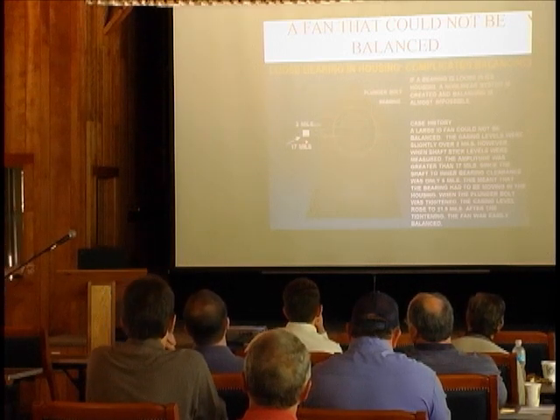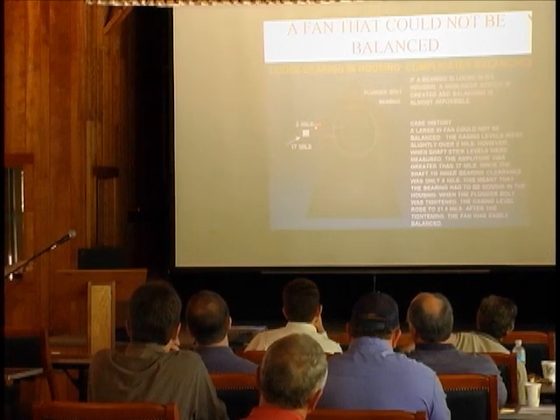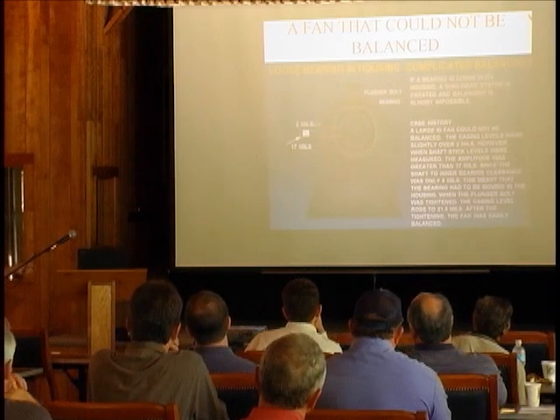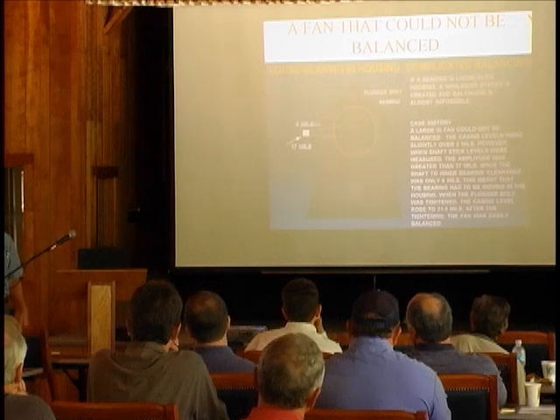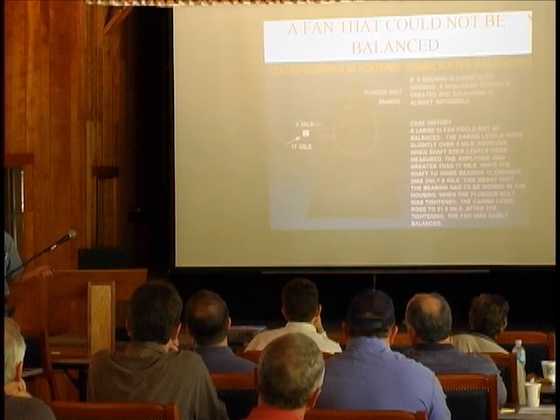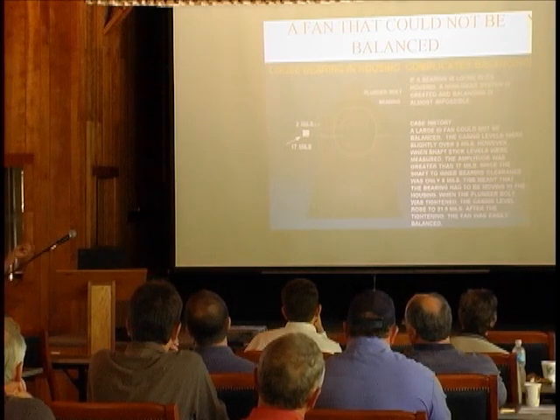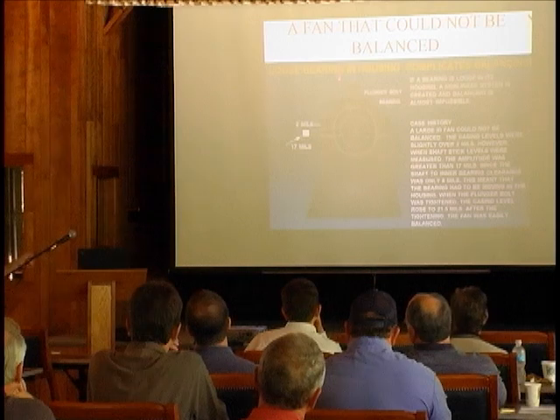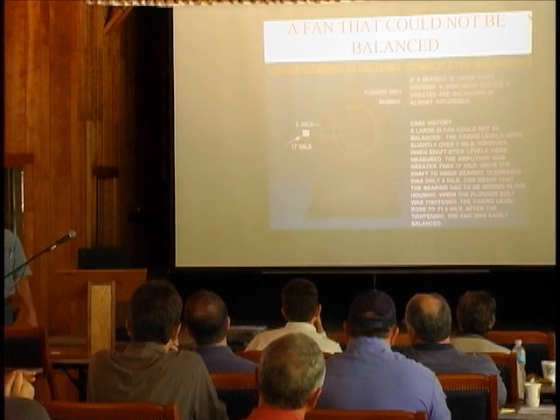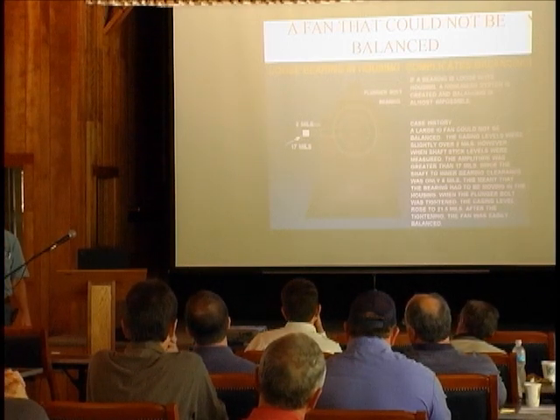So anyway, there was 2 mils on the casing, but when I took the shaft measurement, there's 17 mils. Well, there's only 8 thousandths bearing clearance. Well, that don't add up. That dog won't hunt at all. How are you getting that when you only got 8 thousandths bearing clearance? There's only one way, and that's if the bearing's loose in the housing. That's the only possibility that you can have here.